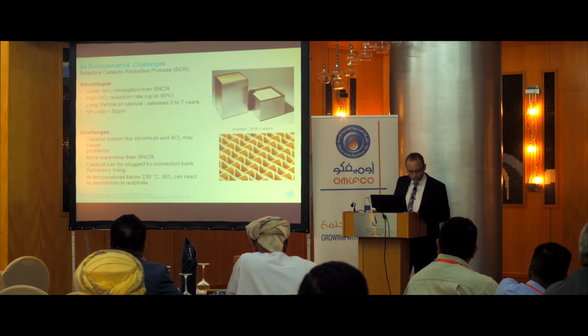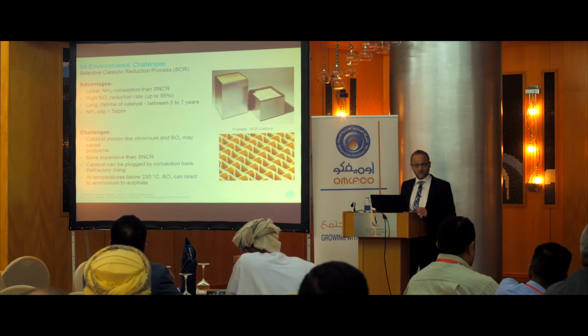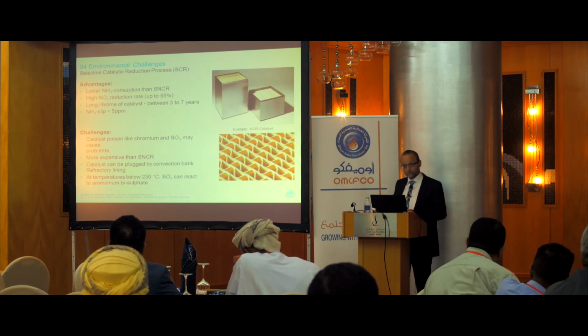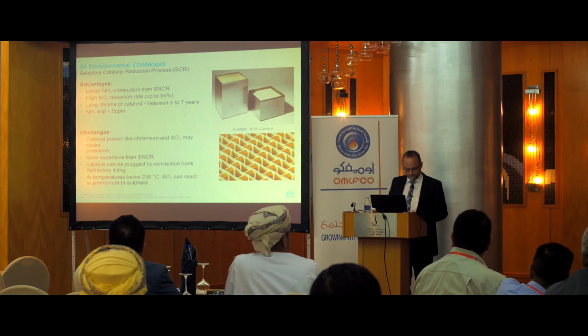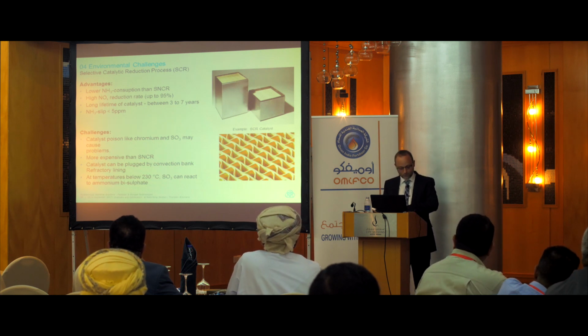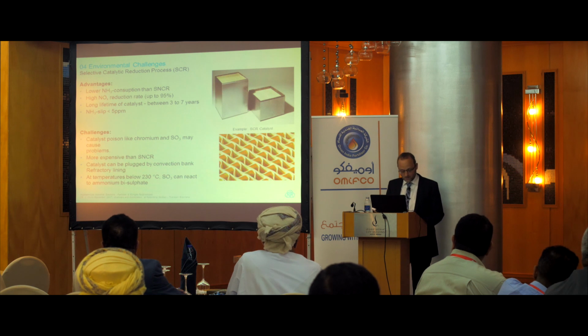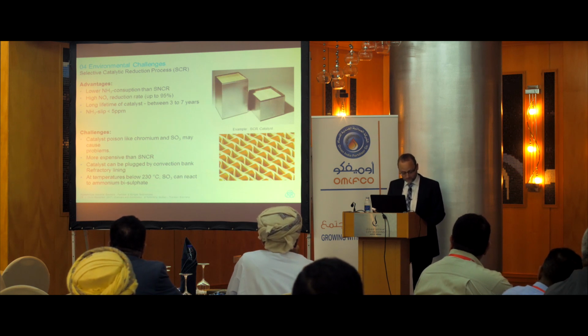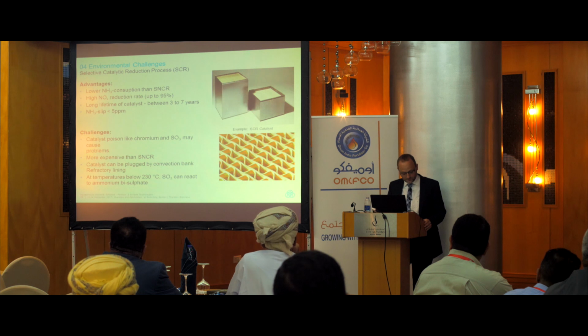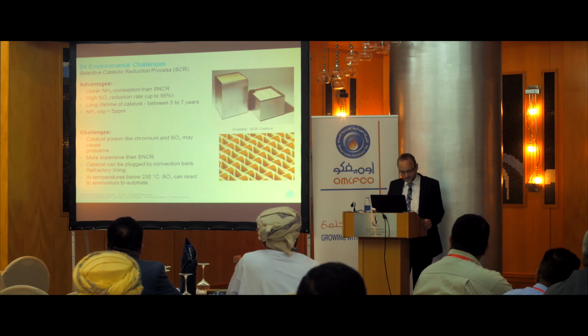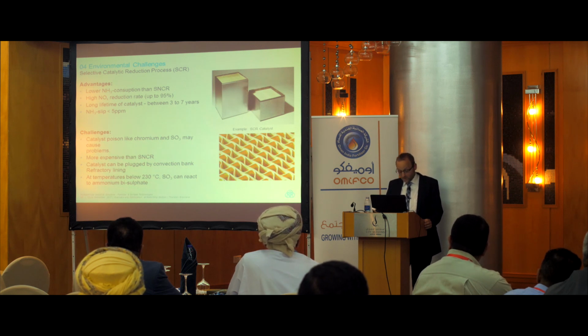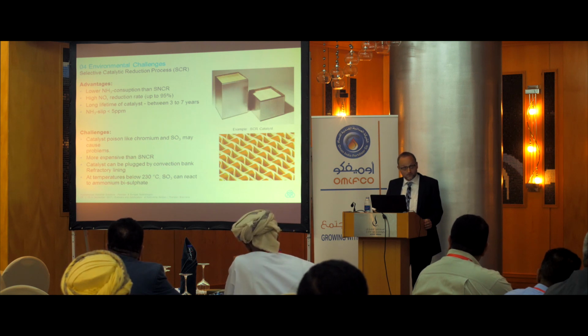So, in order to achieve NOx emissions lower than 90 or 80, which we have shown right now, which we can do for the burners, one has to install an exhaust gas treatment, a selective non-catalytic reduction or a selective catalytic reduction. The difference is the existence of the catalyst and the position of the ammonia water injection. Ammonia water is typically used for this unit. As an alternative, one can also take a urea solution.